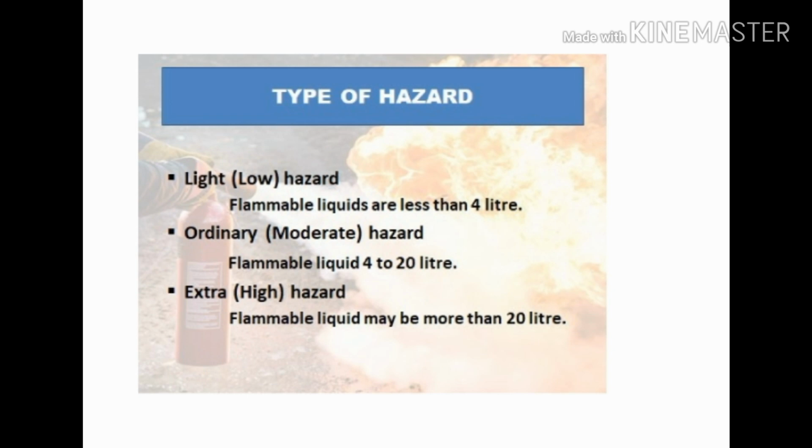Now the types of hazard. There are 3 types of hazards: light or low hazard, flammable liquids less than 4 liters; ordinary or moderate hazard, flammable liquids 4 to 20 liters; extra or high hazard, flammable liquid may be more than 20 liters.